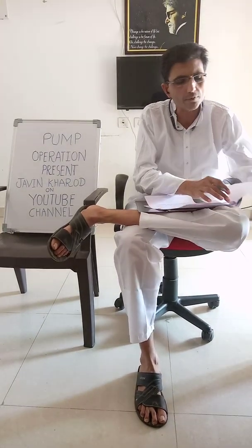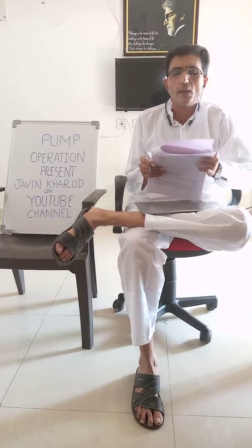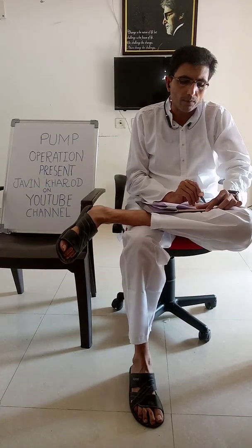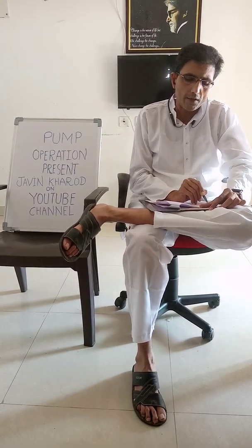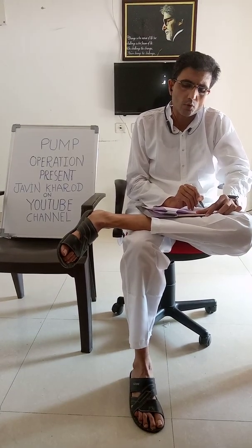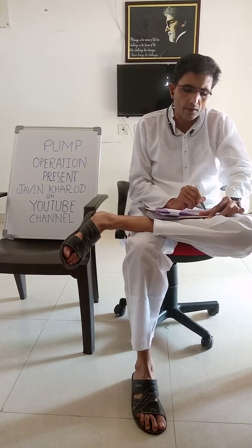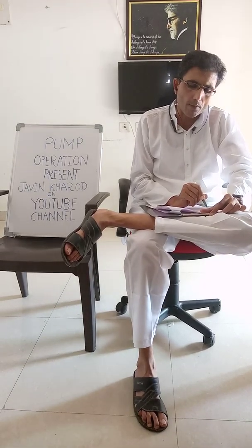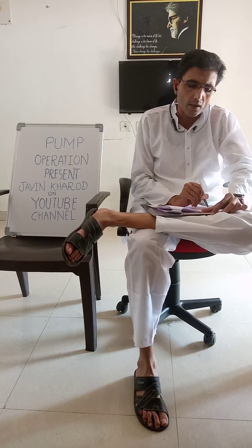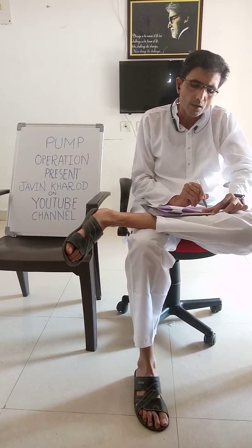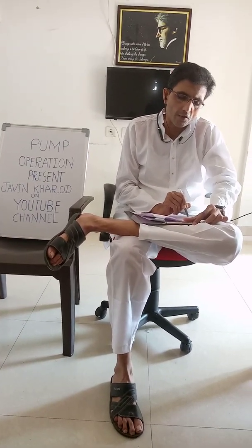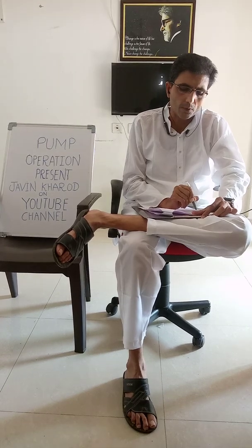Now, what is a mixed flow pump? Mixed flow pump, as the name suggests, has a function between a radial and axial flow pump. The fluid experiences both the radial acceleration and lift and exits the impeller somewhere between 0 to 90 degrees from the axial direction. As a consequence, mixed flow pumps operate at a higher pressure than axial flow pumps while delivering higher discharge than radial flow pumps. The exit angle of the flow dictates the pressure head discharge characteristic in relation to radial and axial flow.